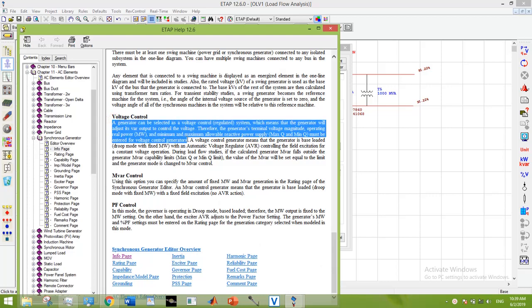A generator can be selected as a voltage control regulated system, which means the generator will adjust its VAR output to control the voltage. Therefore, the generator's terminal voltage magnitude, operating real power, and minimum and maximum allowable reactive power supply (MaxQ and MinQ) must be entered for voltage control generators.